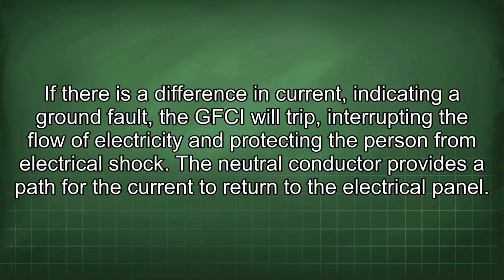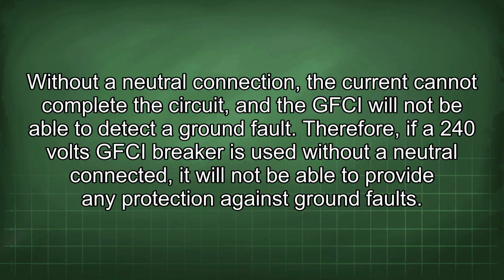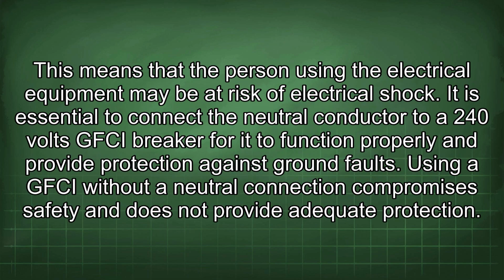The neutral conductor provides a path for the current to return to the electrical panel. Without a neutral connection, the current cannot complete the circuit, and the GFCI will not be able to detect a ground fault. Therefore, if a 240 volts GFCI breaker is used without a neutral connected, it will not be able to provide any protection against ground faults. This means that the person using the electrical equipment may be at risk of electrical shock.